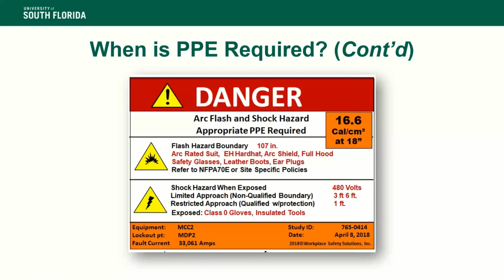Shock hazard when exposed is giving you the volts. Limited approach, non-qualified boundary, 3 feet 6. Restricted approach, qualified with protection, 1 foot. And exposed is telling you it's class 0, which is the minimum you can have for a PPE class. Insulated tools is what this technician requires you to have if you're going in for a shock hazard.